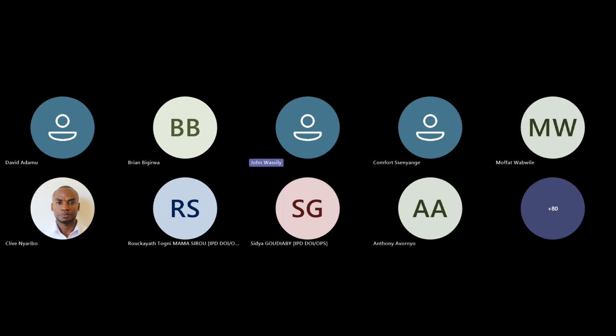Some tests in clean room qualification should be performed in both conditions, at rest and in the operational or dynamic state. For example, viable and non-viable particle counting should be performed in both conditions, for all cleanliness grades, not only grade A and B which are most critical, but also grade C and D.